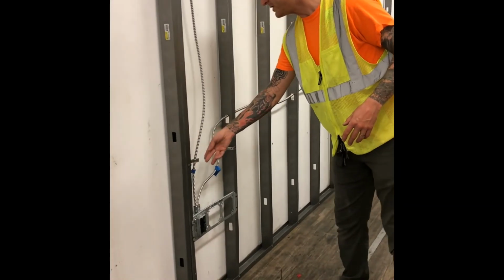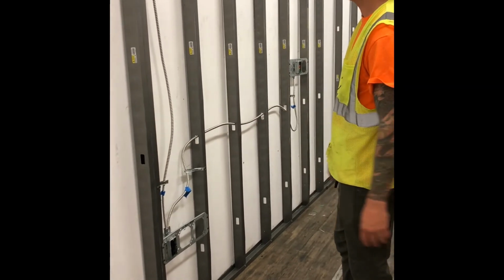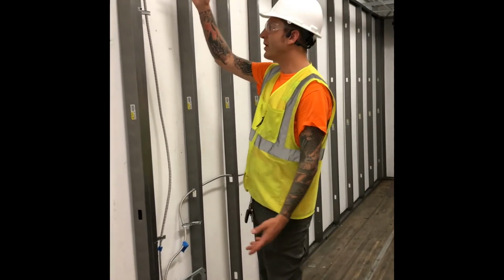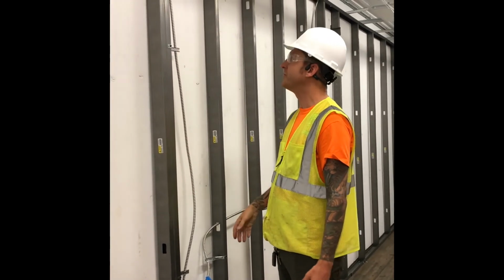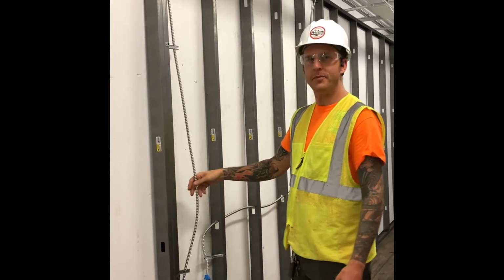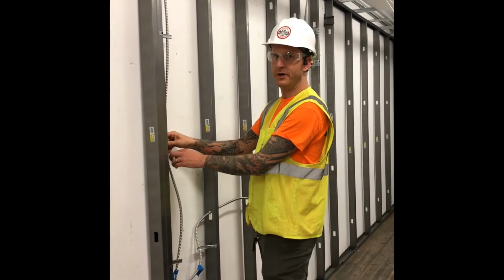Like we talked about earlier, first thing you want to look for is making sure you've got your supports within 12 inches of the box. And even though code might allow 6 feet between the next one, if it's flopping in the breeze like this, go ahead and put an extra one on there. It's not going to hurt.